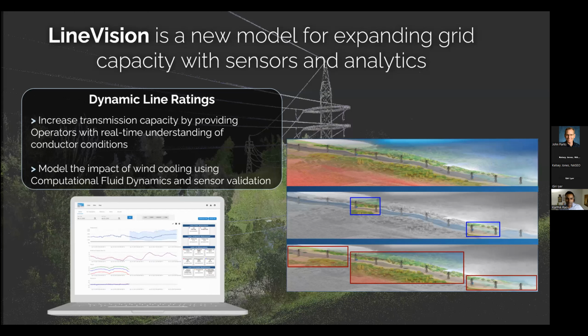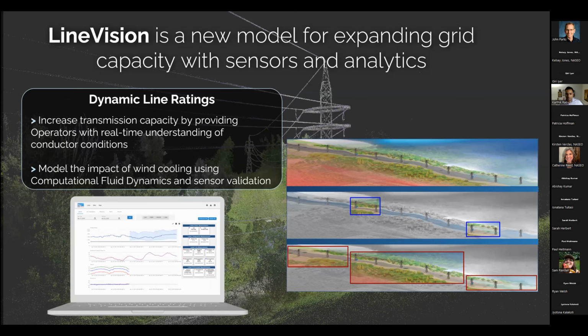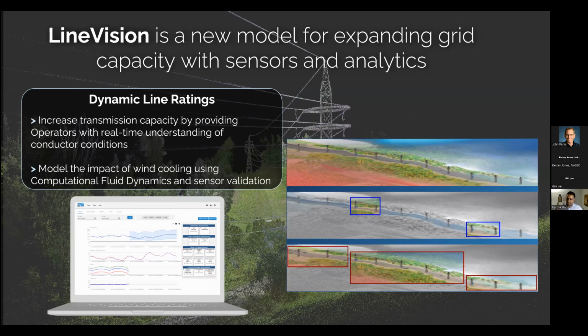Drilling in a bit on dynamic line rating—what is DLR? I'm sure many of you have heard of this technology, but I'll explain. Every conductor, every transmission line has a rating: the maximum current you can run through it safely before it overheats. Traditionally, that rating has been calculated using a static line rating, where we take worst-case-scenario assumptions—picture the hottest day of the year, no wind blowing, and the line already at risk of overheating. What's the maximum current you can push through under those conditions before exceeding the line's maximum operating temperature? Whatever that number is becomes the fixed line rating, 365 days a year.